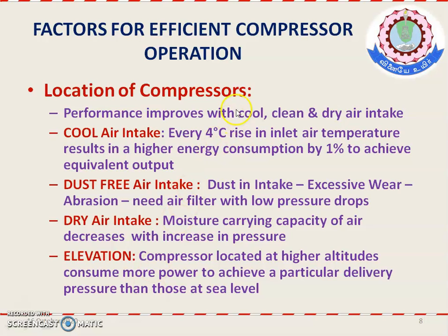And here, what are all the factors you need to consider for efficient operation of a compressor? The main thing is the location of the compressor. Performance improves with cool, clean and dry air. So if you prefer an environment with all these constraints, which has cool air, clean air and dry air, the performance of the compressor will increase. Cool air intake: how it reflects on the efficiency means every 4°C rise in inlet air temperature results in higher energy consumption by 1%.